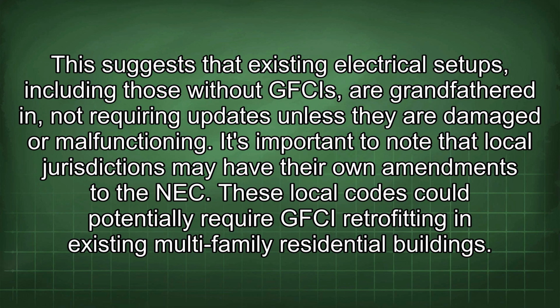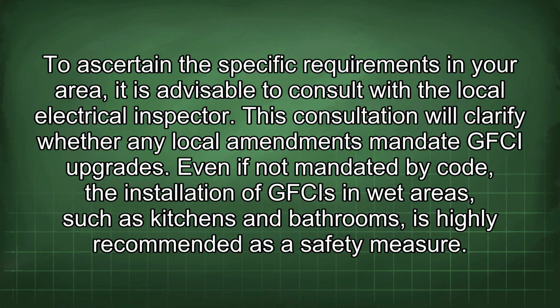These local codes could potentially require GFCI retrofitting in existing multifamily residential buildings. To ascertain the specific requirements in your area, it is advisable to consult with a local electrical inspector. This consultation will clarify whether any local amendments mandate GFCI upgrades. Even if not mandated by code, the installation of GFCIs in wet areas such as kitchens and bathrooms is highly recommended as a safety measure.